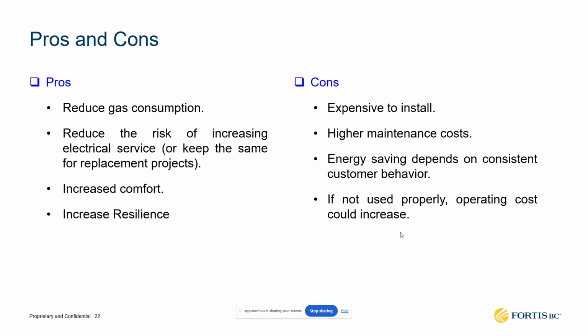One thing we discovered in our pilot is that we established a switchover temperature, and the contractor who is installing the equipment makes sure that the switchover temperature is as per our specifications. And then after he leaves, the user can change those settings, or they can even override it for a valid reason, with the thinking that it's going to be temporary, but then they leave it on, and all the savings that we were expecting are not happening. So depending on the cost of the utilities in BC, the cost of electricity is around twice the cost of gas. If you're running into situations where your heat pump is running at a low efficiency due to outdoor temperature, you can have an increase in your utility cost.